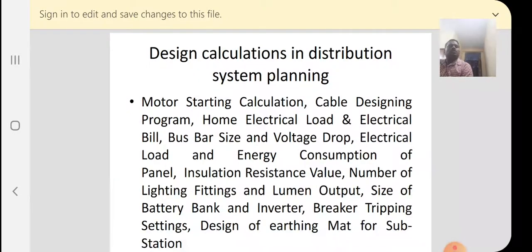The third is the voltage drop criteria. This is used for developing torque, meaning there are some losses at the torque end, so we need higher voltage for torque generation when starting any motor, generator, or machine. Based on these three criteria, we calculate the size of the cable.